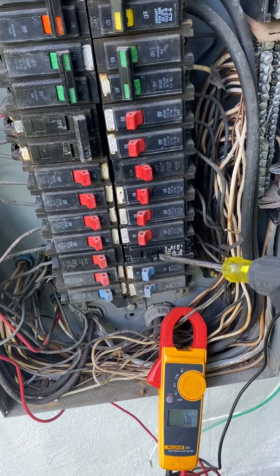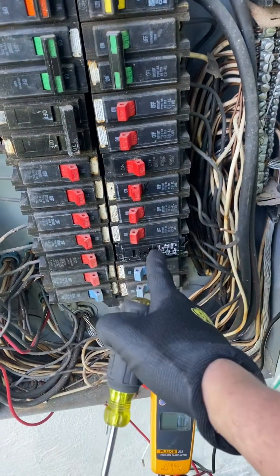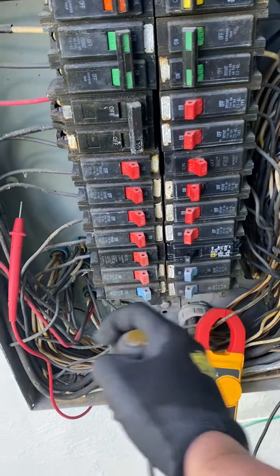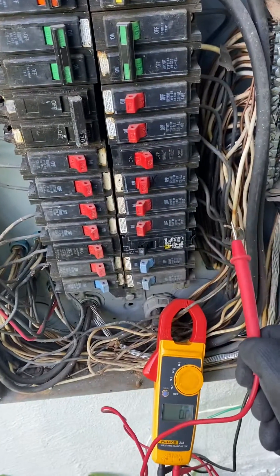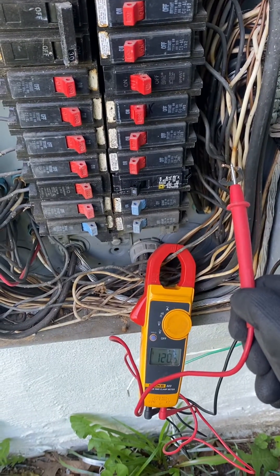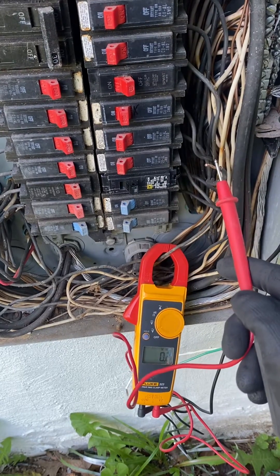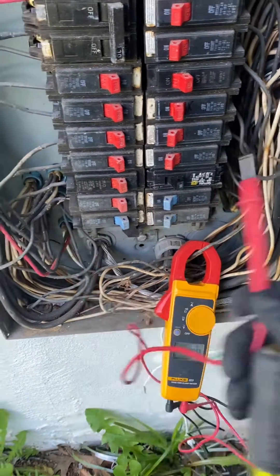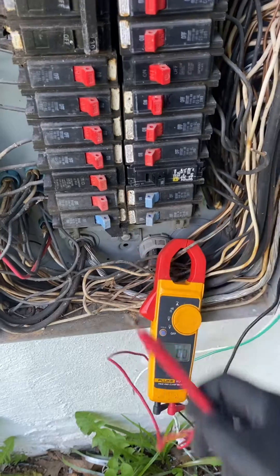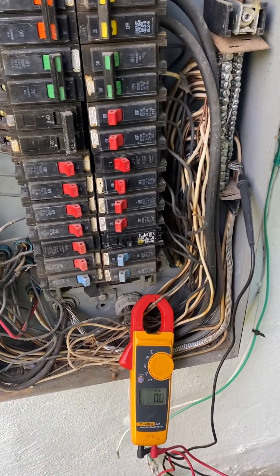When I unplug this one and turn this breaker on, this wire is going to be energized. I'll demonstrate — turn that on. Reading 120 volts, 120 volts. Turn it off, nothing trips. Like I said, it's bumping phases together and causing a short.